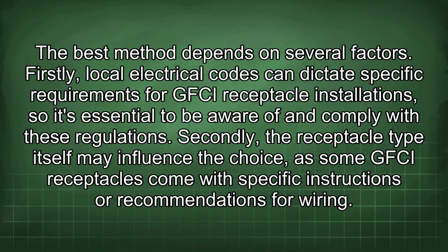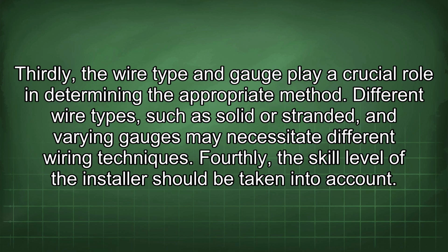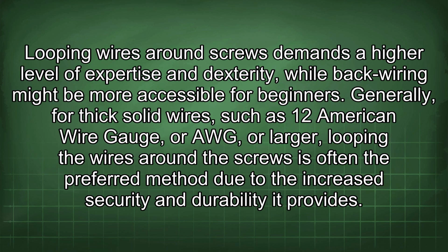The best method depends on several factors. Firstly, local electrical codes can dictate specific requirements for GFCI receptacle installations, so it's essential to be aware of and comply with these regulations. Secondly, the receptacle type itself may influence the choice, as some GFCI receptacles come with specific instructions or recommendations for wiring. Thirdly, the wire type and gauge play a crucial role in determining the appropriate method. Different wire types, such as solid or stranded, and varying gauges may necessitate different wiring techniques. Fourthly, the skill level of the installer should be taken into account. Looping wires around screws demands a higher level of expertise and dexterity, while backwiring might be more accessible for beginners.